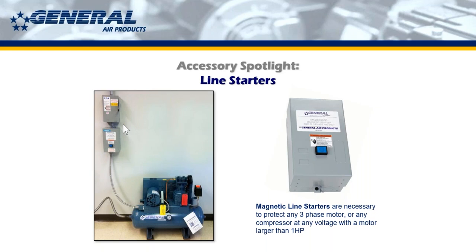A bit about these two. Sometimes they can be a pain in the neck when it comes from an ordering standpoint. We do not include them with our compressors because we think it's more important to send compressors in the field that have different voltages available, so that when they get to the job site, if it's 115, 208, or 230, you can wire for any of those. The problem is that a line starter is voltage specific. So until we know exactly what voltage you're wiring for and what unit you're using with, then we can put in the correct components to make the line starter work.